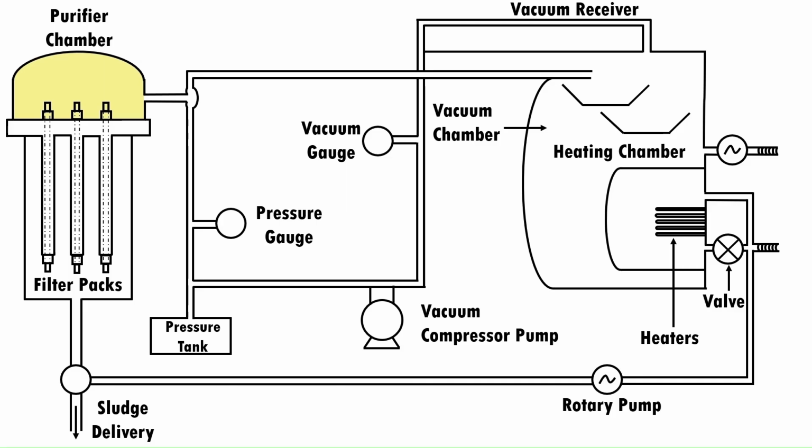The purified oil from the purifier enters the vacuum tank. Here it is dropped into open trays. The oil is thus exposed to dehydrating. Vacuum is maintained by an electrically driven high vacuum pump. Finally, the clean and pure oil is collected from the outlet.